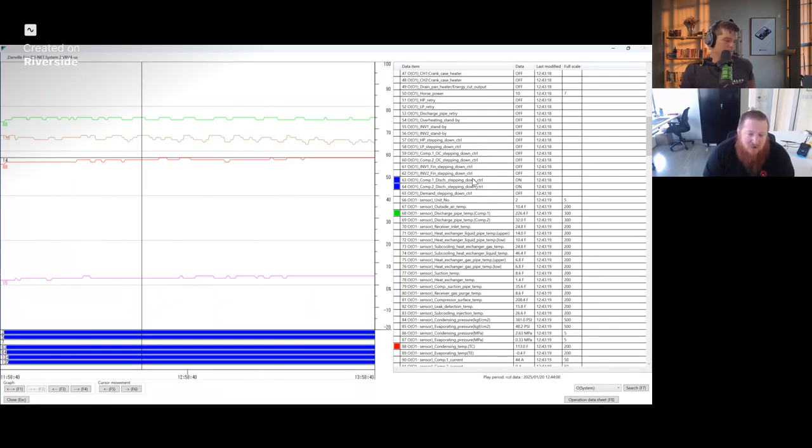We're hoping we're coming into the expansion valves on the outdoor unit as a liquid so that they can cause the pressure drop so that we can use the outdoor coil to pick up heat, but we didn't pick up heat. So I always equate that to what side of the system the other side of the heat exchanger on the outdoor is when you're in heat mode. It's on the suction side. So the reason why that's getting so cold is because we're just pulling on it. There's nothing there, and we just keep pulling on it.